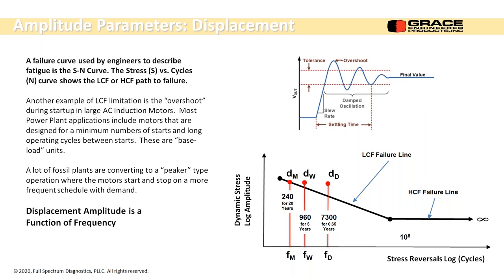People designed for that. So for a baseload plant, you might say, well, we can plan on having one start and stop cycle every month. So for 20 years, that's 240 cycles. And I can plot that on my LCF curve. So I can say, there's my max. I don't want to run anywhere above that.